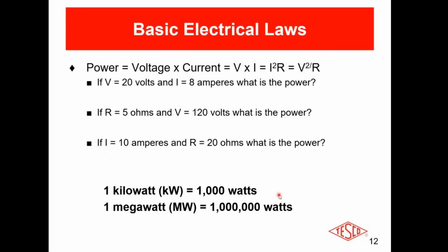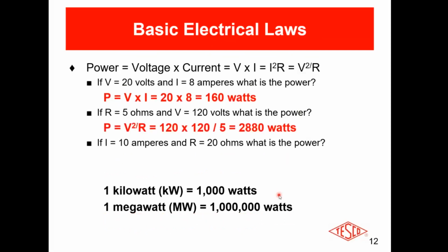Okay? So power equals voltage times current. And again, I go through a couple of quick examples when I'm doing an in-person meter school. 20 volts, 8 amps, what's the power? 160 watts. 5 ohms, 120 volts, what's the power? 2,880 watts. 10 amps, 20 ohms, what's the power? I squared R, it's 2,000 watts. Of course, we don't usually work in watts. We're usually working in kilowatts. So that's 2 kilowatts. And if you're getting more into generating or renewables, it's megawatts, which would be 1,000,000 watts.